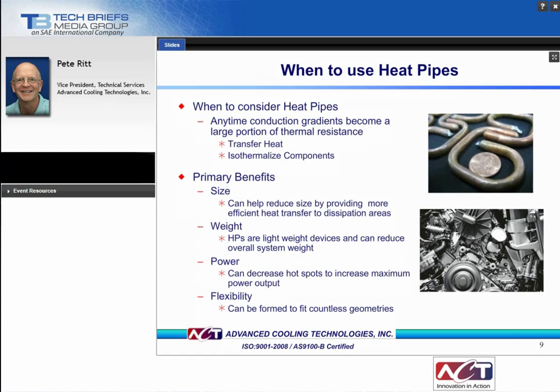And in terms of flexibility, heat pipes can be formed to fit countless geometries. The typical bending radius for a heat pipe is 3 times the outside diameter, and they can be flattened to 2/3 the outside diameter. An operating heat pipe bent around a penny can be seen in the upper right.